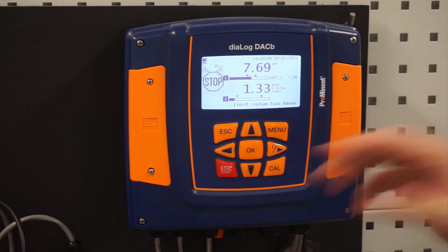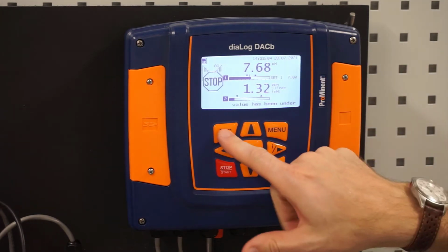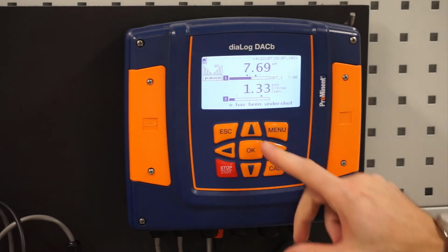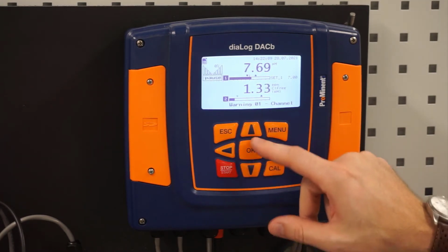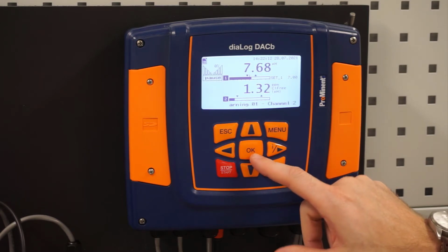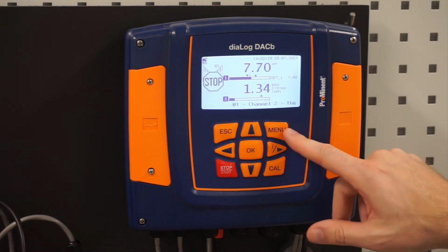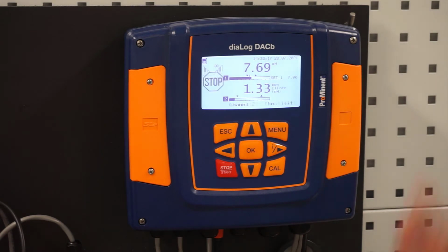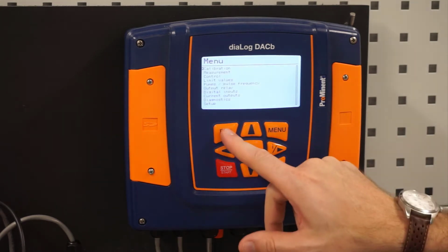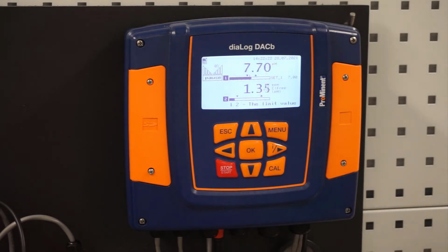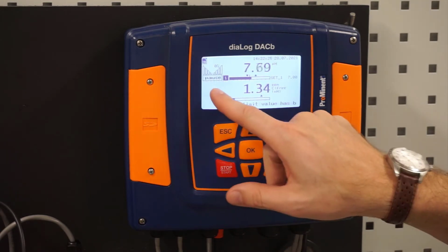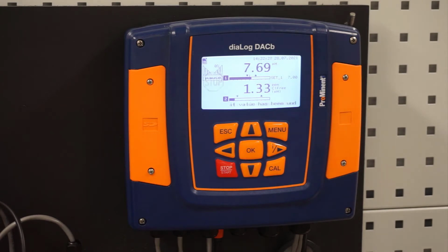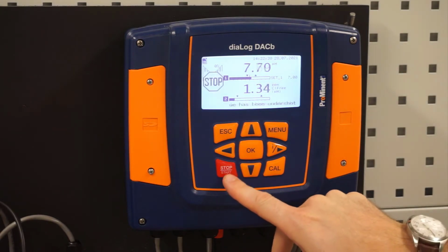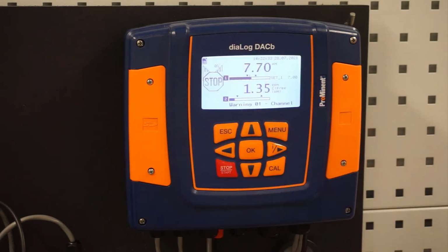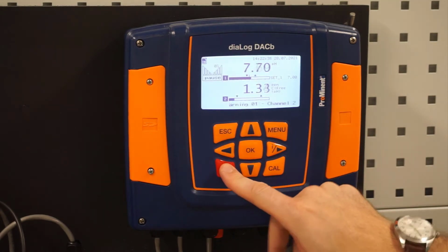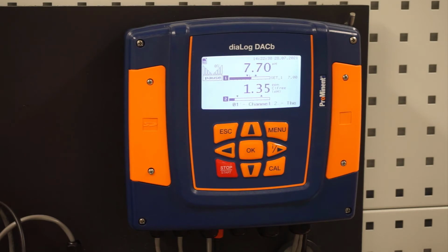The escape button is going to escape us out of programs. We're all the way out, so hitting escape's not going to do anything for us. We have arrows for navigation. OK is going to confirm anything that we want to change or enter a screen. The menu button is going to allow us to access the menu screen. We can escape out of it by hitting escape. Start stop button down here. You can notice that our controller is flashing a stop sign. That means somebody has come up here and hit the start stop button. When we do that, it's going to stop all control. So I'm just going to hit the start button.